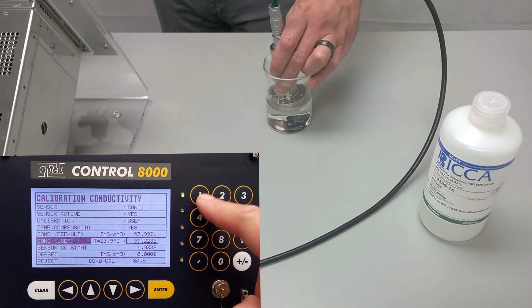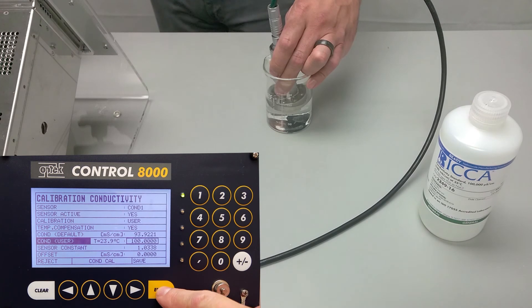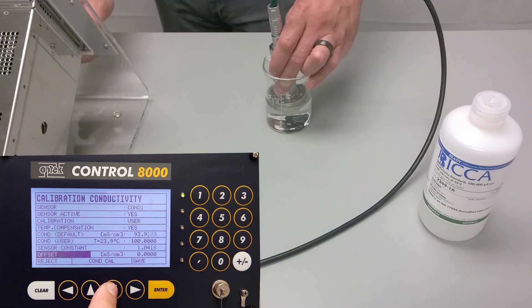Enter our nominal value for our conductivity solution of 100, press enter on that, and then scroll down and save our changes.